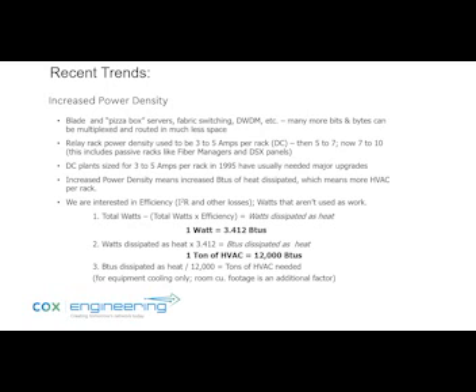So when you design a critical facility in terms of how much cooling you're going to need, that's where you would design a certain amount of tons of HVAC to what is the proposed heat load, and you would actually take a look at the floor space and calculate basically how many racks you could put in there.